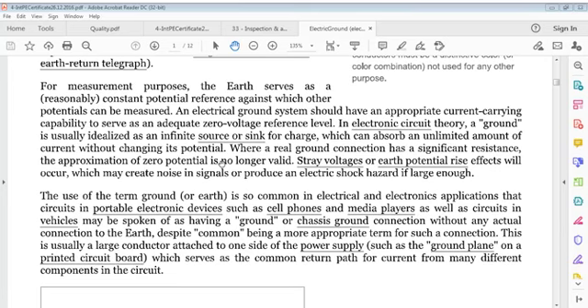Zero voltage reference level. What it says: an electrical ground system should have an appropriate current carrying capacity or capability to serve as an adequate zero voltage reference level. In electronic circuit theory, a ground is usually idealized as an infinite source or sink for charge, which can absorb an unlimited amount of current without changing its potential.